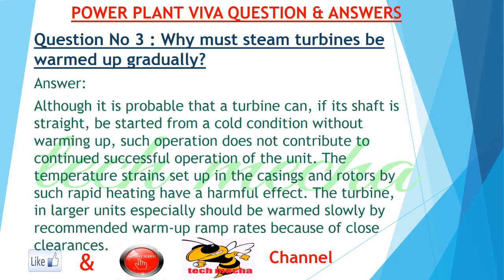Question number 3: Why must steam turbines be warmed up gradually? Answer: Although it is probable that a turbine can, if its shaft is straight, be started from a cold condition without warming up, such operation does not contribute to continued successful operation of the unit. The temperature strain set up in the casings and rotors by such rapid heating has a harmful effect. The turbine, in larger units especially, should be warmed slowly by recommended warm-up ramp rates, because of close clearances.